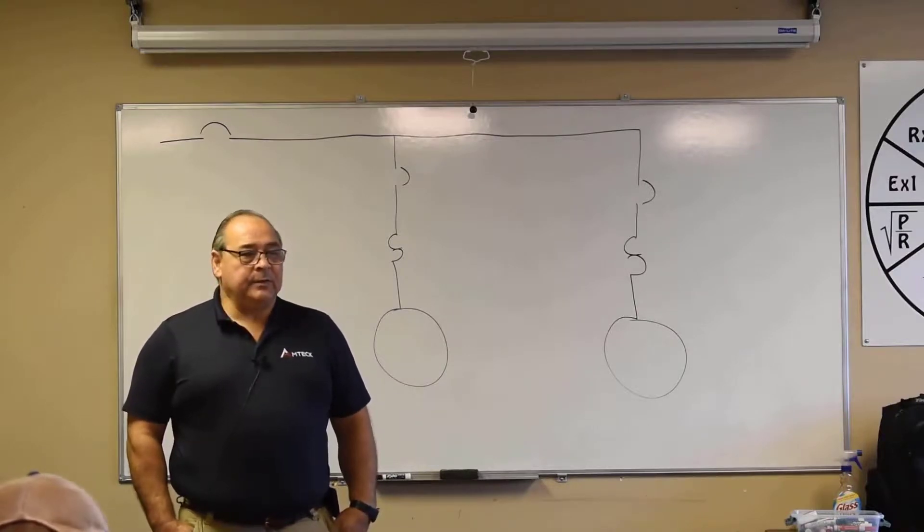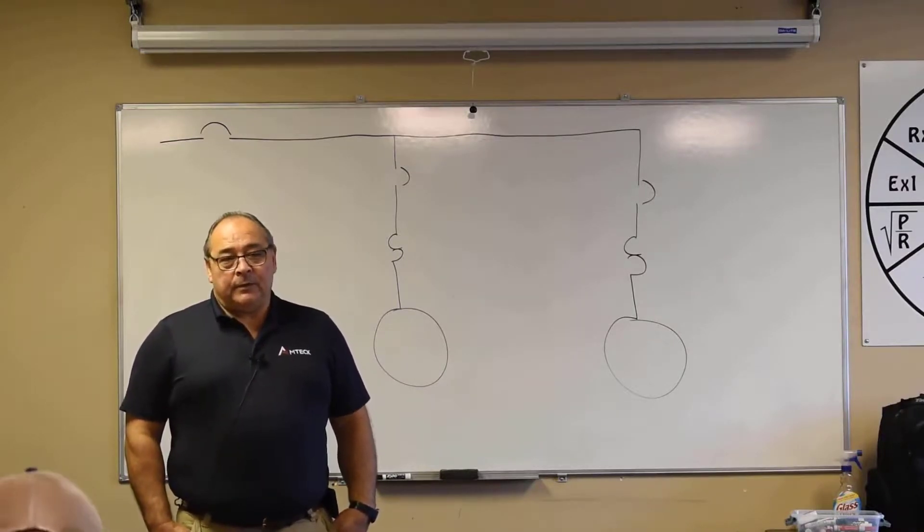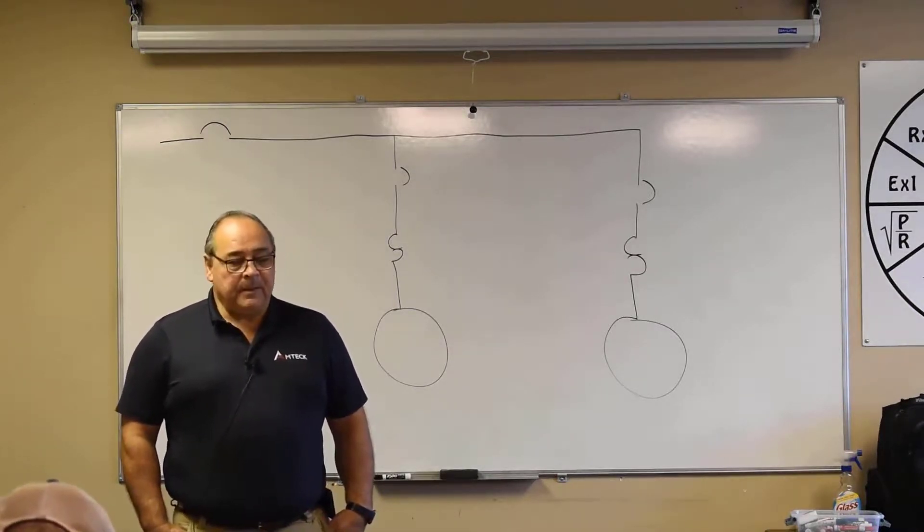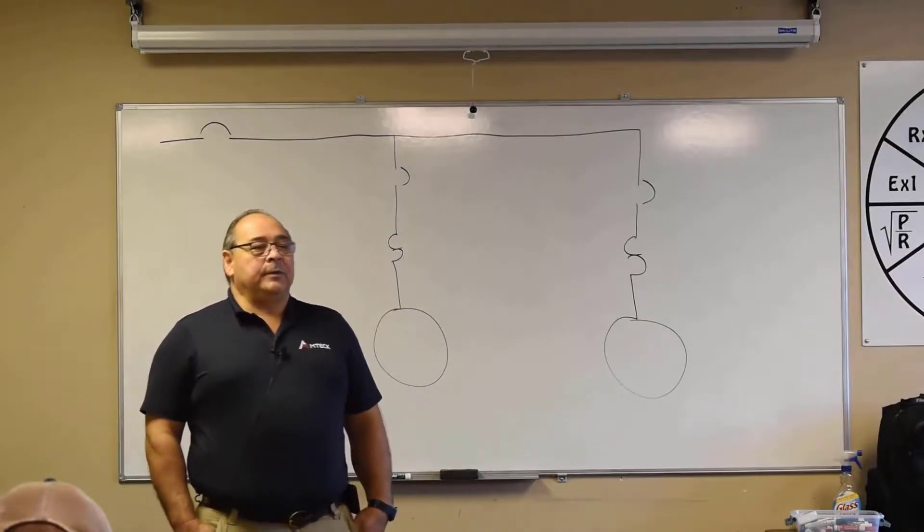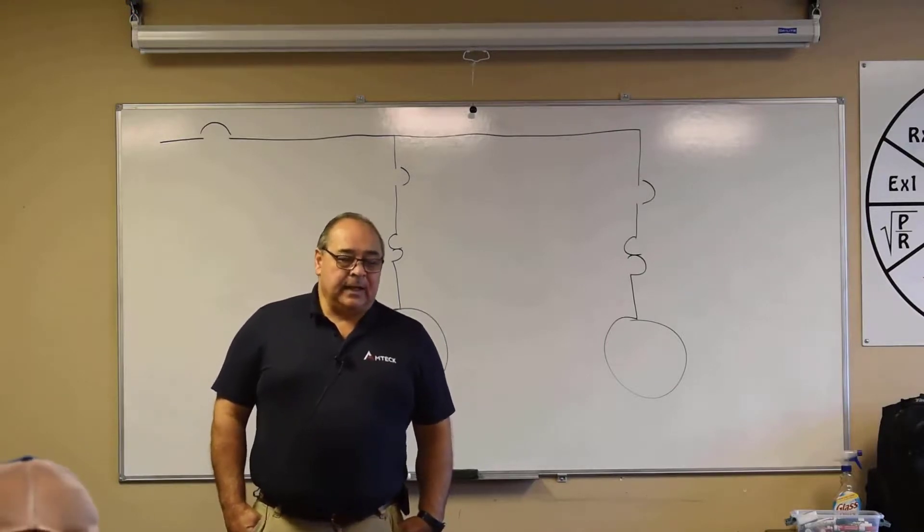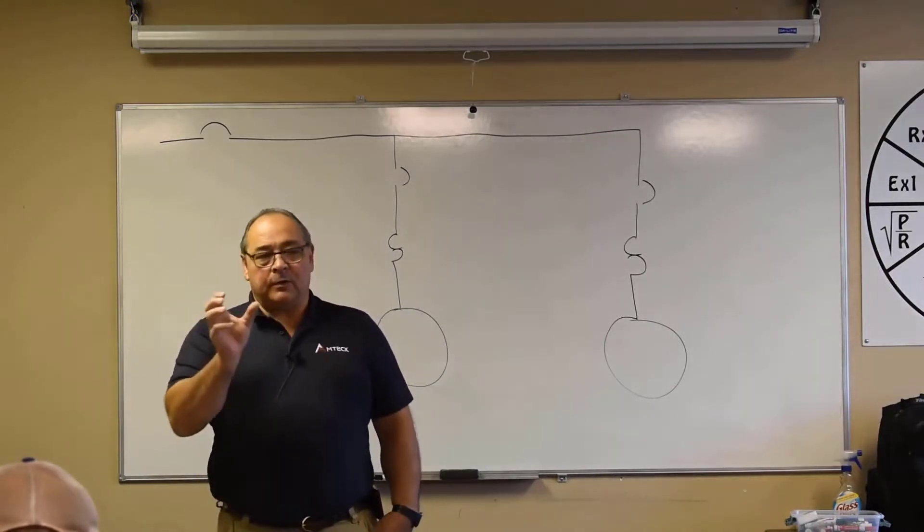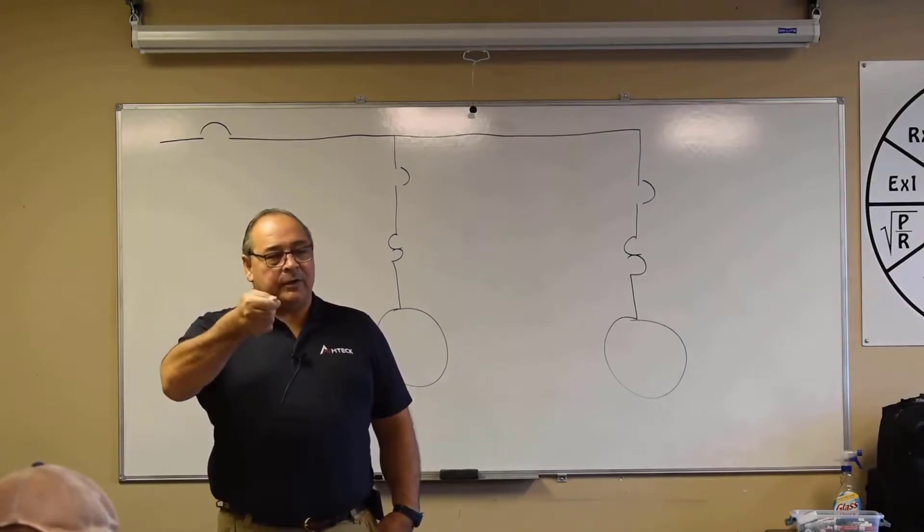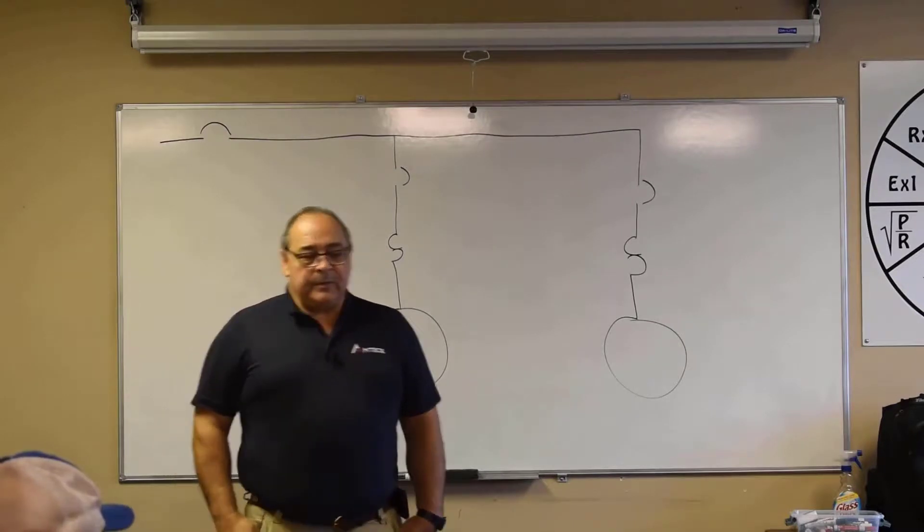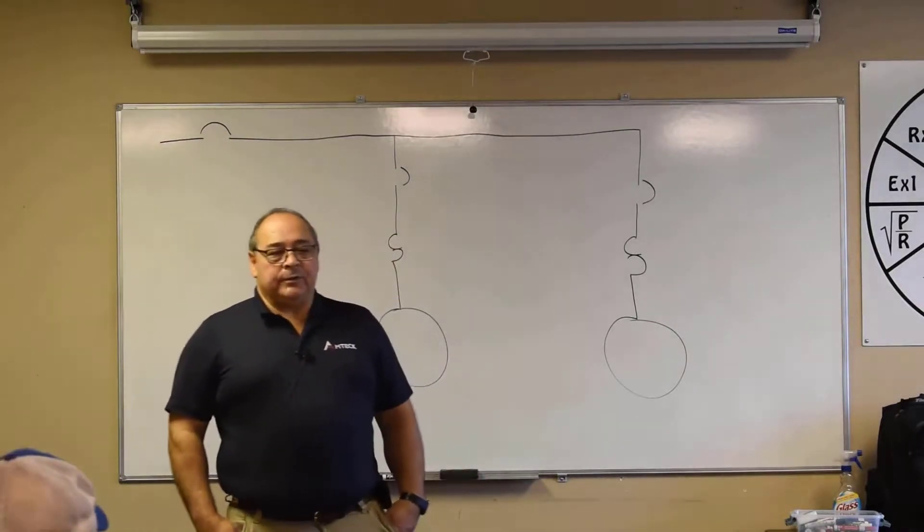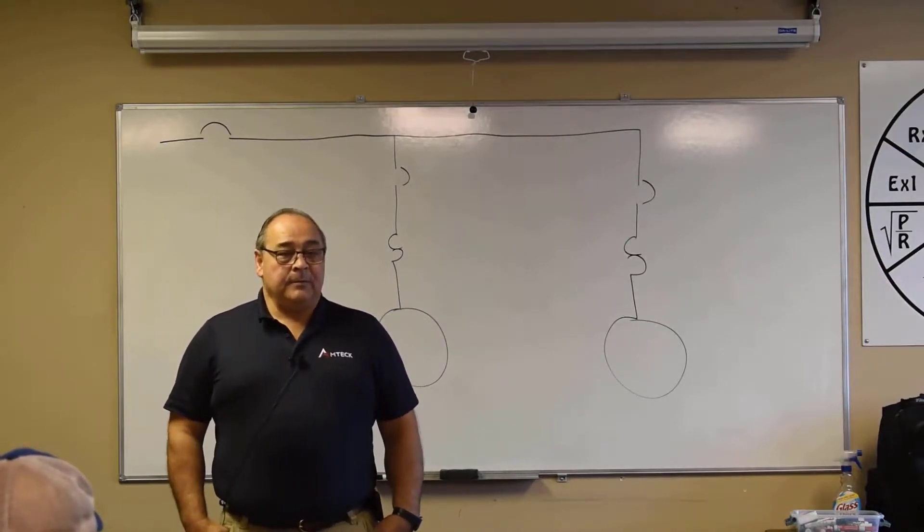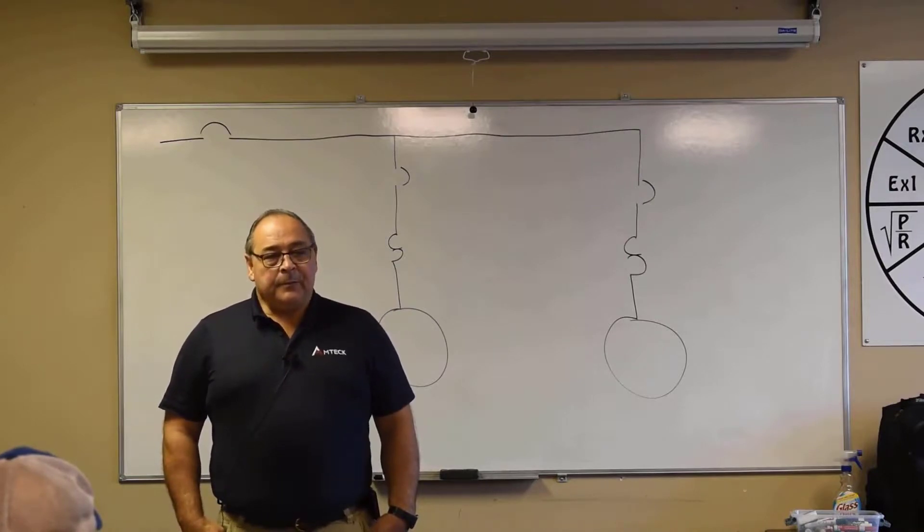Now let's talk about overload protection versus fused and circuit breaker. When you hear the word overload or overcurrent, you think of fuses and circuit breakers. Now, in a motor circuit, the overload protector is that little thing that's got the reset button on it, generally speaking. For the IEC style of this, it's the overload relay. It's got a little dial on. You can dial it up or dial it tuned in, tune it up, down, up, whatever you want to do. For the NEMA style of these, it's got those replaceable heaters. Exchangeable heaters. You take the heaters out, you bolt new ratchet type heaters in. You guys play with motors, you understand that. But that's the overload. That's what protects that circuit in an overcurrent issue.